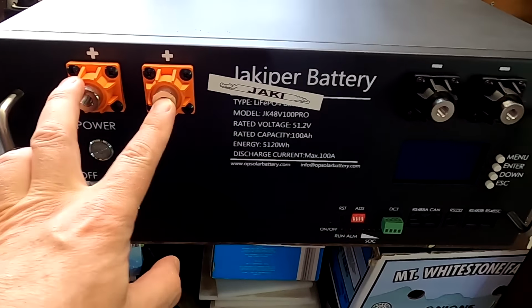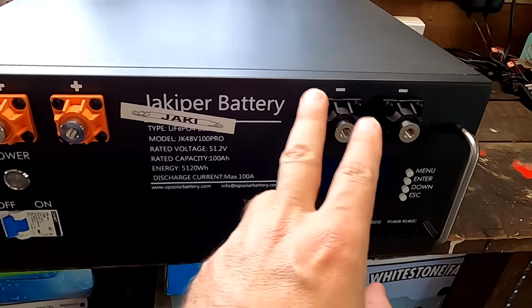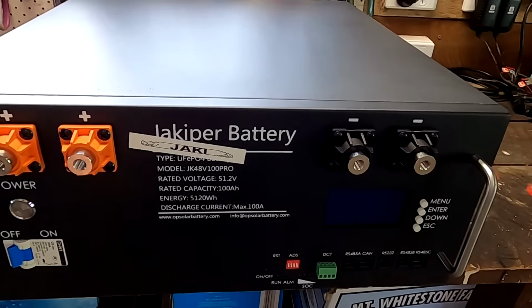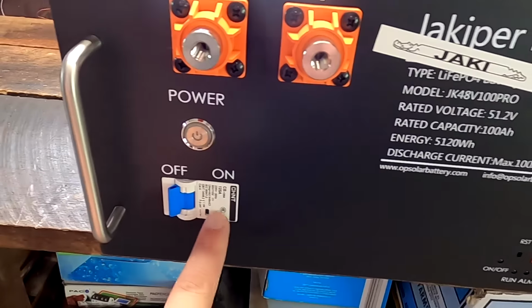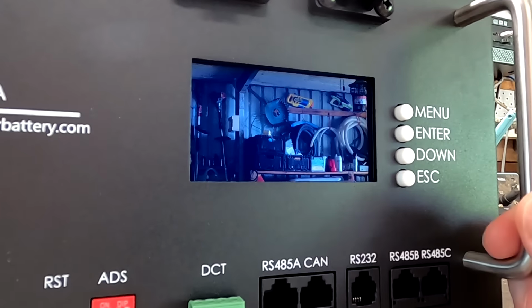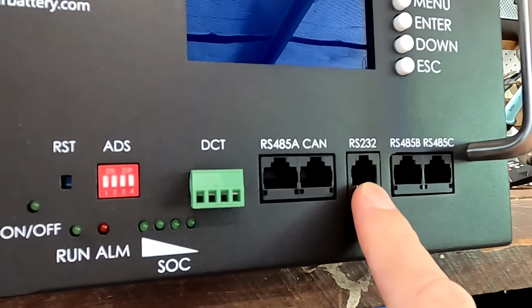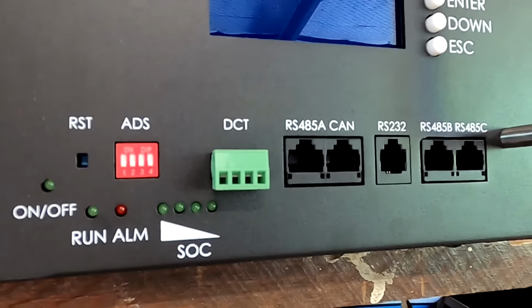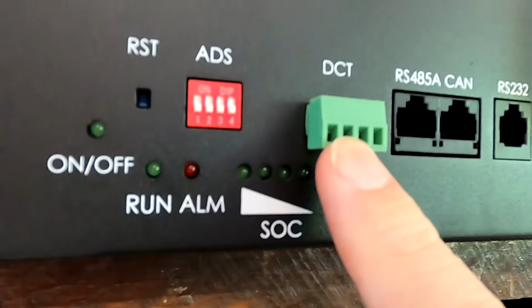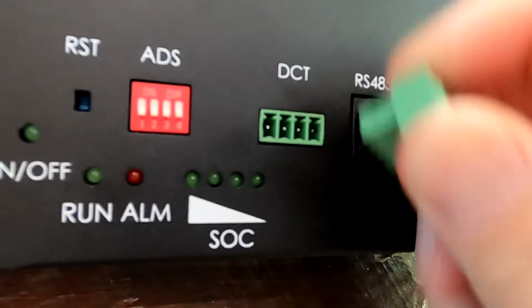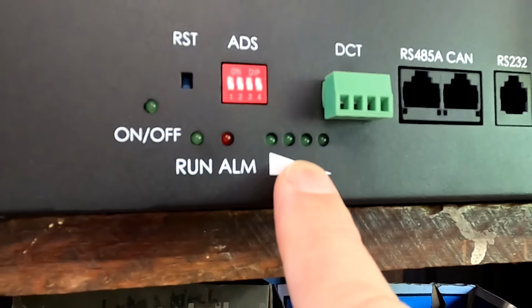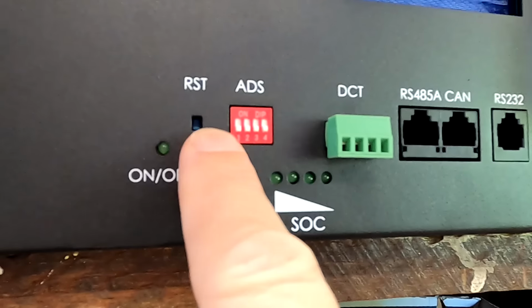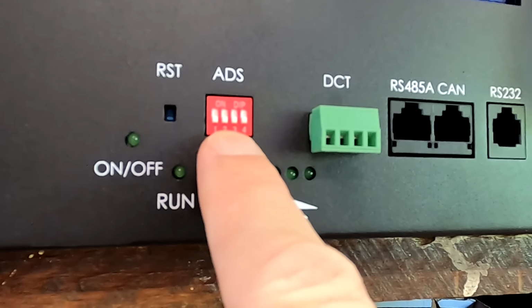So I've got 2 positive terminals, 2 negative terminals, so we can daisy chain them together if you have more batteries in parallel. I've got a power on off button, a circuit breaker. Yes, so this is how a circuit breaker looks like. BMS display with 4 menu buttons, RS485, RS232 and CAN communication. Relay contacts including a terminal, state of charge gauge, alarm, run LED, reset button and dip switches for parallel communication. And some handles left and right.